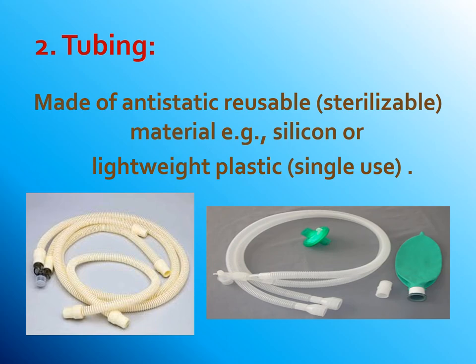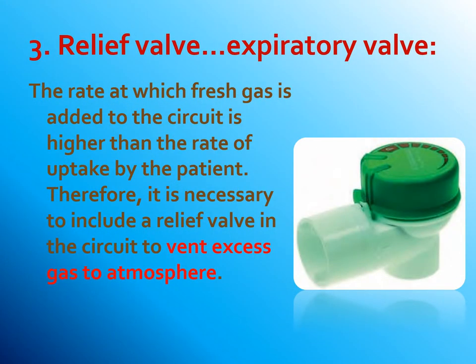Tubing is made of anti-static reusable sterilizable material, such as silicone, or lightweight plastic single-use material. The relief valve, or expiratory valve: the rate at which fresh gas is added to the circuit is higher than the rate of uptake by the patient. Therefore, it is necessary to include a relief valve in the circuit to vent excess gas to the atmosphere.